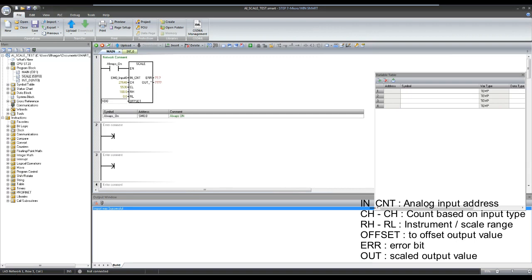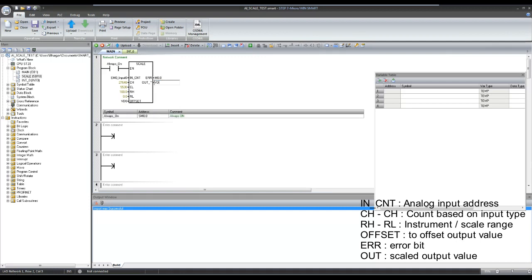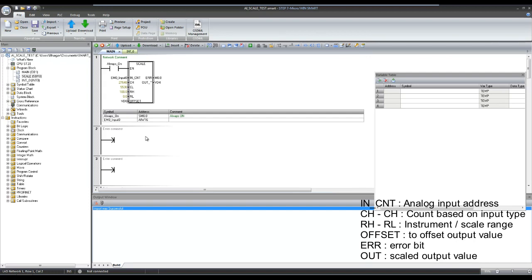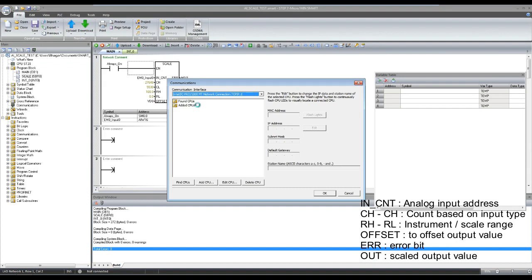Offset can be used in case your transmitter milliamps is not matching to the actual value. Error bit will be high when input count is out of the defined count CH and CL. And at out, scaled analog value will be available in real data type. Now let's download the program and test the block.